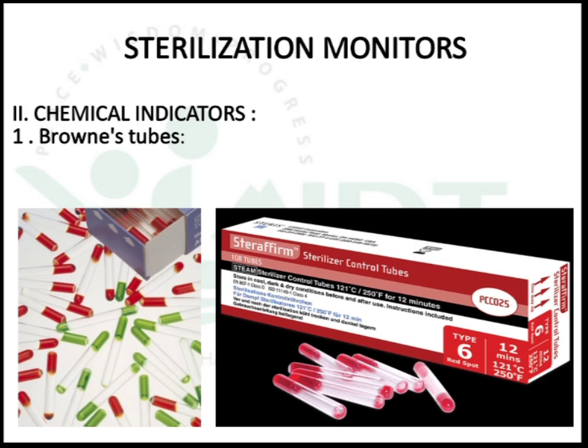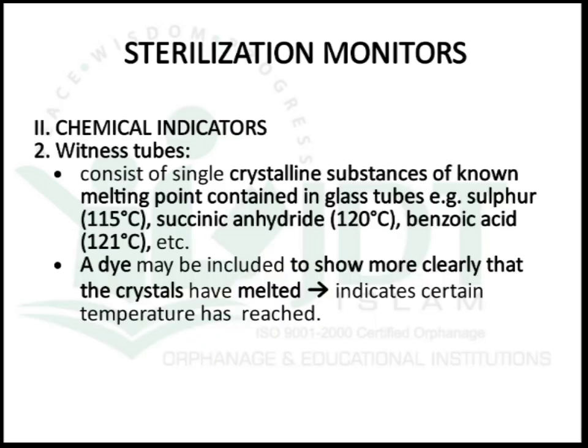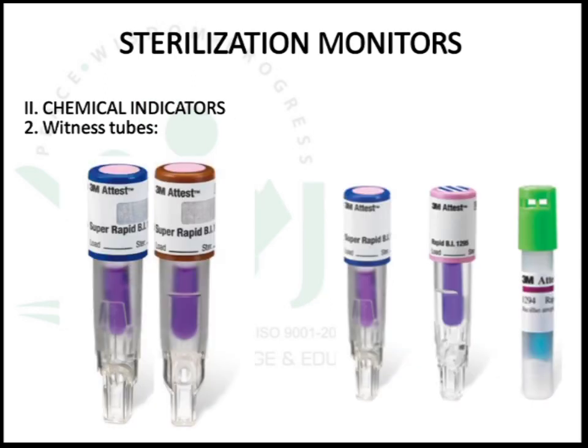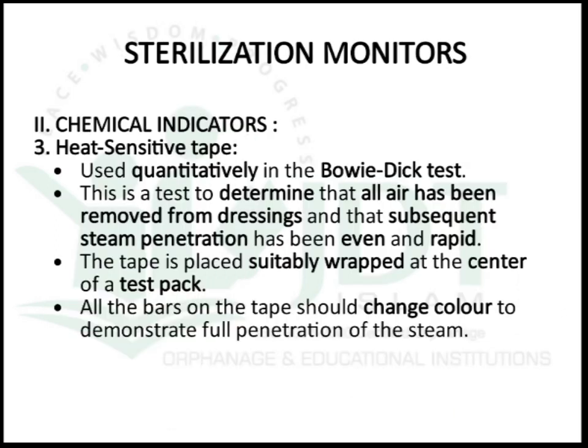The witness tube consists of a single crystalline substance of known melting point contained in a glass tube — for example, sulfur which melts at 115°C, succinic anhydride which melts at 120°C, and benzoic acid which melts at 121°C. A dye may also be included to show more clearly that the crystal has melted, so the color change indicates that a certain temperature has been reached.